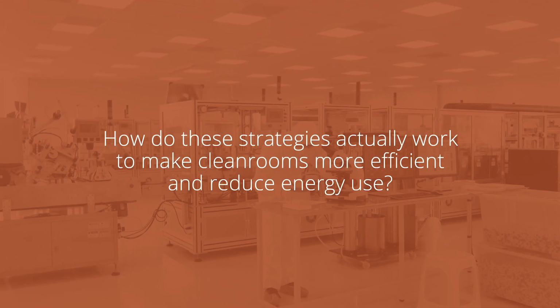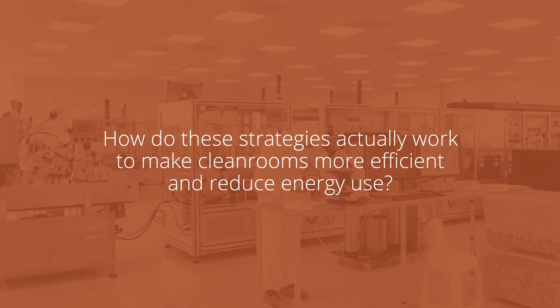How do these HVAC strategies actually work to make clean rooms more efficient and reduce energy use? So specifically to HVAC, you're going to have either variable volume control devices, meaning you'll have an ECM motor, an electrically controlled motor, or you'll have a VFD, and all of those types of devices that allow you to modulate the airflow from a maximum to a minimum within a range, give you the ability to actually change the velocity of the airflow from top to bottom or left to right. And in doing that, again, changing the actual total air change in the space. So it saves energy by reducing the amount of horsepower you need, which is a result of reducing the amount of air changes to meet the specific need in a specific zone for a specific number of particles per cubic foot.